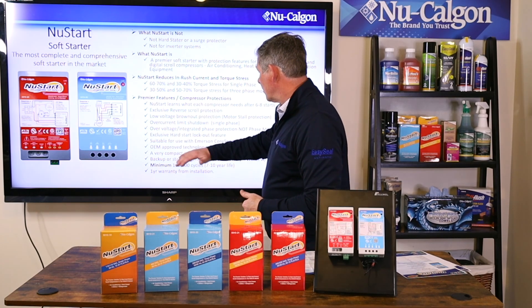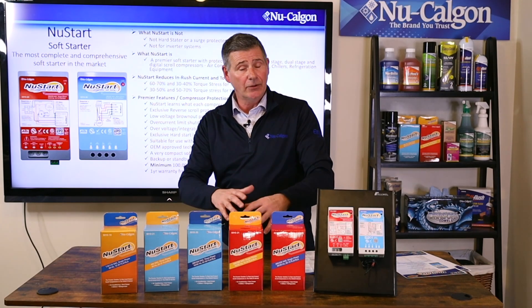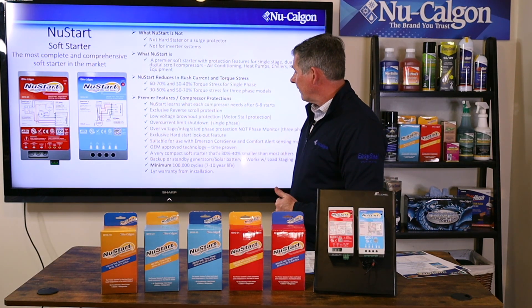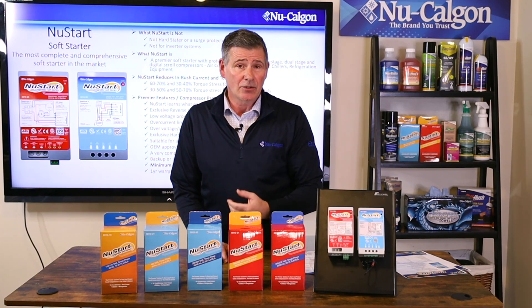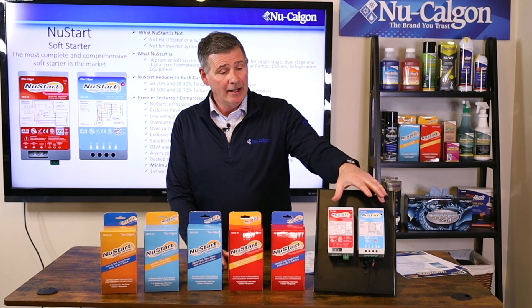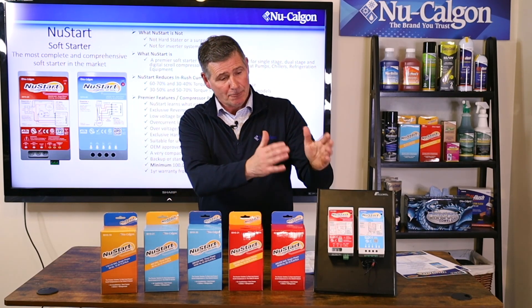We have an exclusive hard start lockout feature. These are also suitable for use with Emerson CoreSense and the Comfort Alert sensing modules. If you have those on the compressor or AC unit, you don't need any fancy wiring or bypassing — these work perfectly with the Emerson CoreSense module. These are OEM approved, time-proven technology, and very compact — about 30 to 40% smaller than other soft starters on the market. You won't need a NEMA enclosure; they fit under the hood next to the capacitor, including in heat pumps, with no additional wiring required.